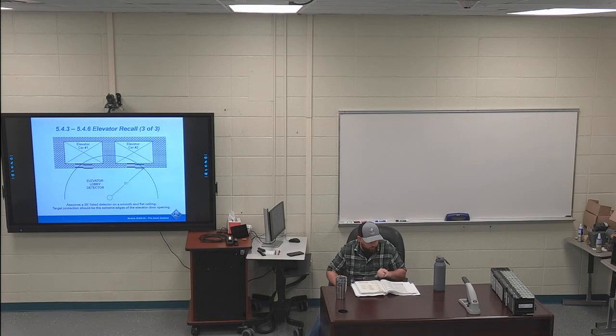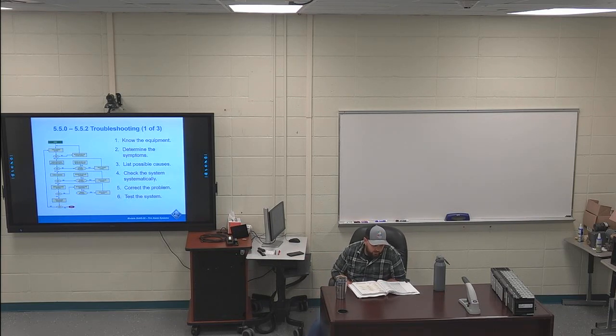Nothing highlighted on page 61. Going on to page 62, the sentence right after the note I've got highlighted. A supervisory signal must be visually and audibly distinctive from both alarm signals and trouble signals. So you can't have a supervisory signal that's like the three tones and a pause, because that's indicative of a fire. Moving on to 550, troubleshooting these systems. Step 1, I have just the first sentence highlighted. First thing you do is you have to know the equipment. Knowing your brand and how they work and what type of system it is, that's step 1 in troubleshooting.